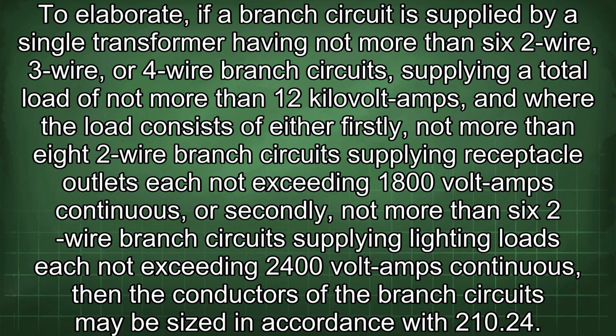To elaborate, if a branch circuit is supplied by a single transformer having not more than 6 2-wire, 3-wire, or 4-wire branch circuits, supplying a total load of not more than 12 kVA, and where the load consists of either, firstly, not more than 8 2-wire branch circuits supplying receptacle outlets each not exceeding 1800 VA continuous, or secondly, not more than 6 2-wire branch circuits supplying lighting loads each not exceeding 2400 VA continuous, then the conductors of the branch circuits may be sized in accordance with 210.24.